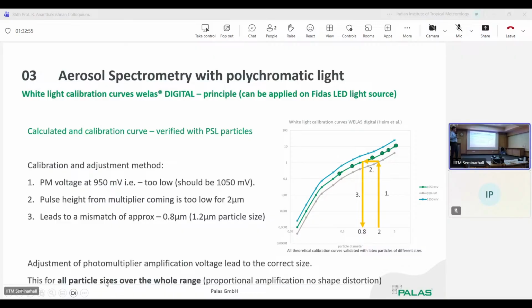Then the complete calibration curve moves due to the amplification of the photomultiplier. So it's only the signal from the photomultiplier finally. Of course, if the light sources are too weak, then we get problems in the lower area because we have no resolution. But the light sources which we use are made for these specific ranges, and we can tune our systems to other ranges by more or less amplification. There are some points where we can amplify even higher to see maybe smaller particles, but then we already have interference with the gas molecules.